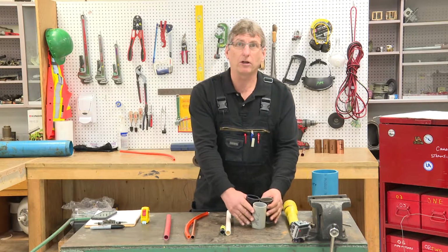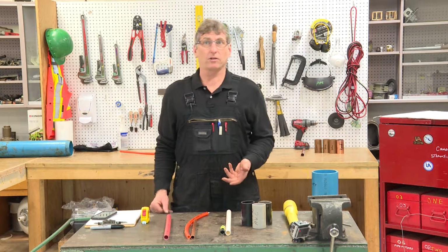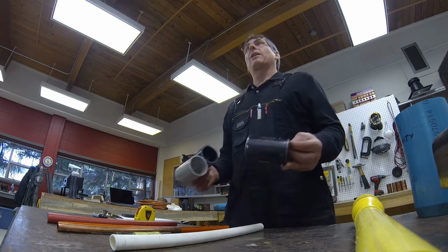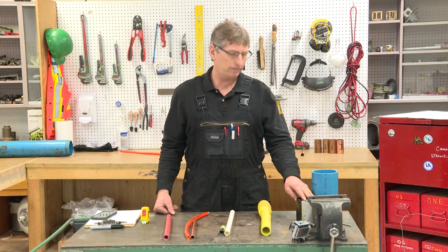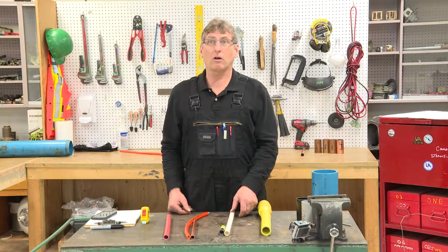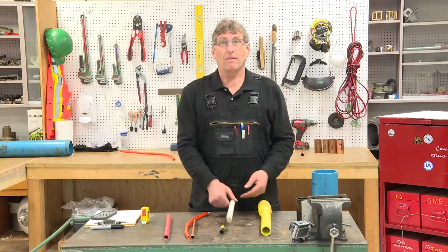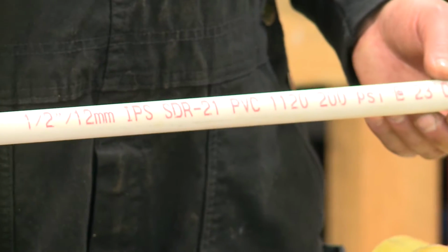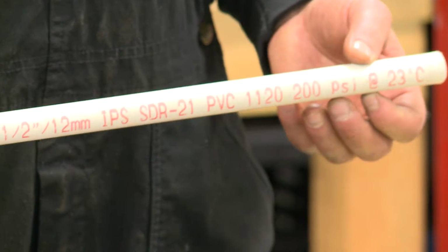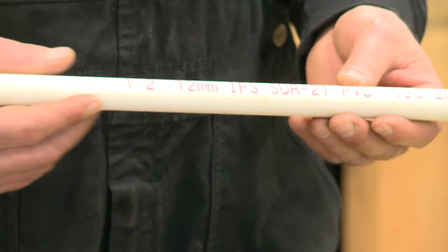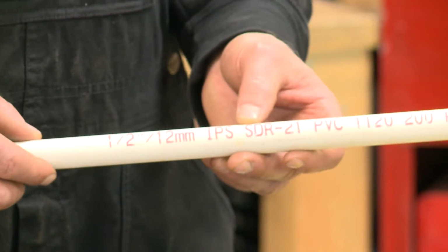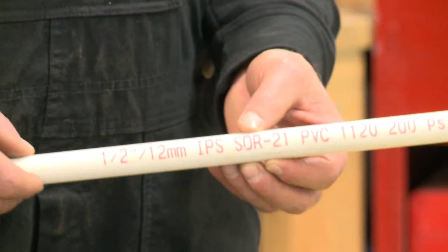So everything that we learned on our IPS tables in the first video related to wall thickness for steel pipe would apply to these plastic products. Don't assume that all PVC pipe uses the pipe schedule system. Quite the contrary. As a matter of fact, PVC, as well as most other plastics, use the standard dimension ratio system. As you can see when you look at some of these examples of plastic pipe and tube, they are stamped with SDR and a number. Others may just say DR and the number.